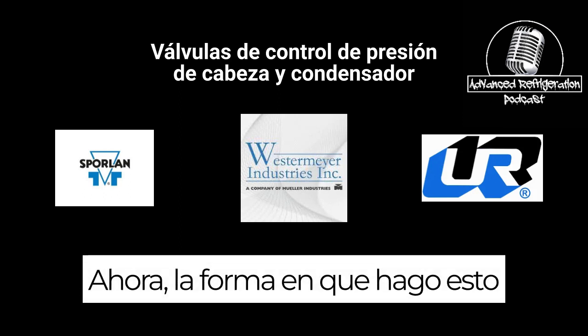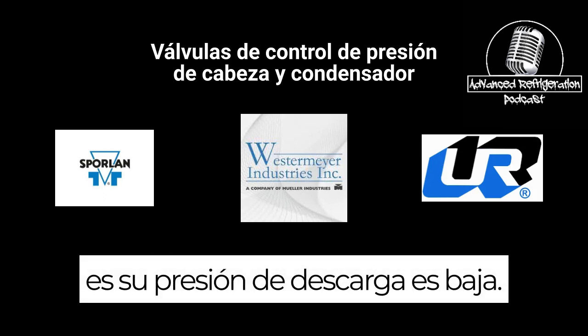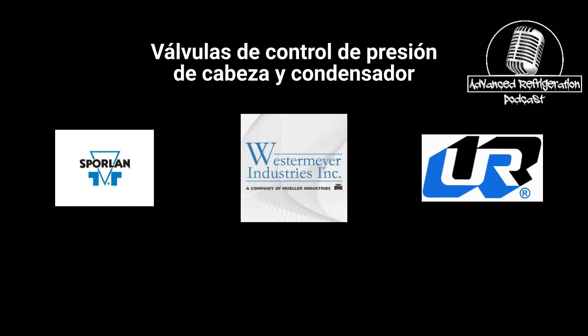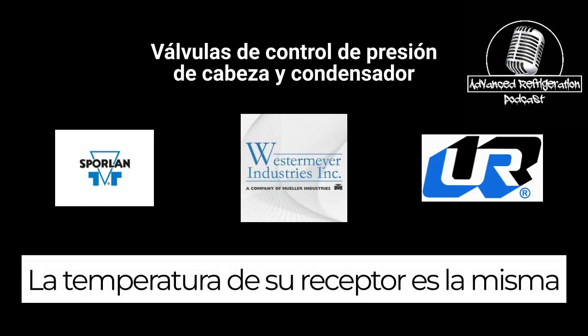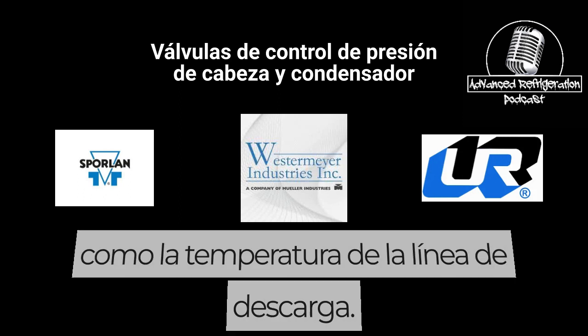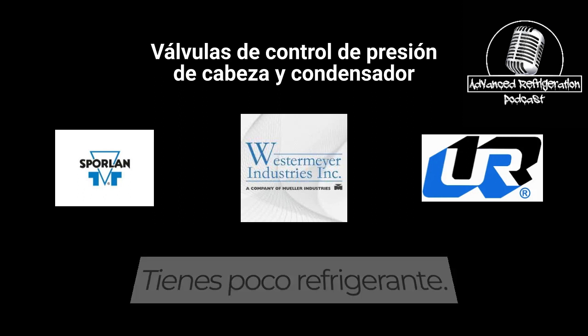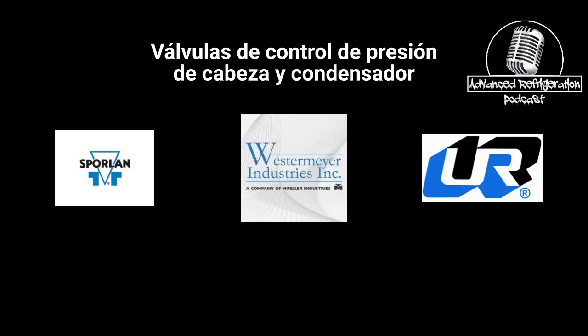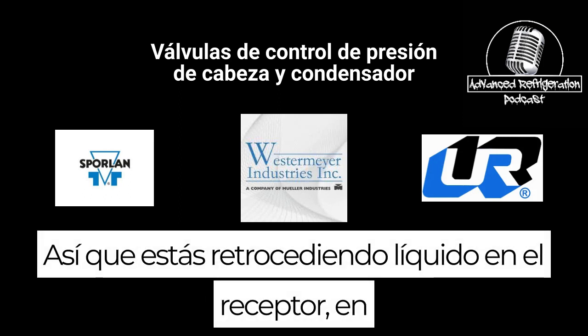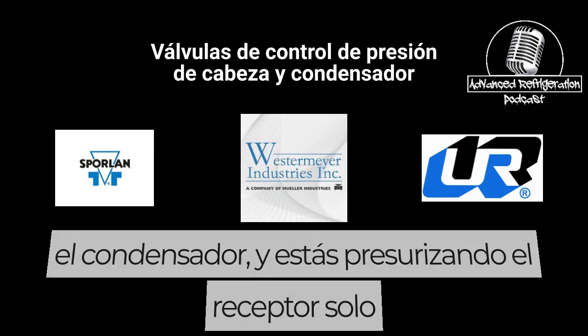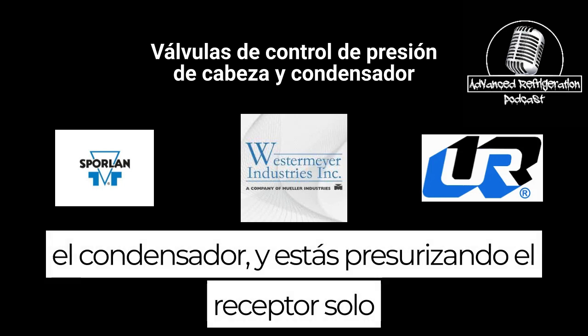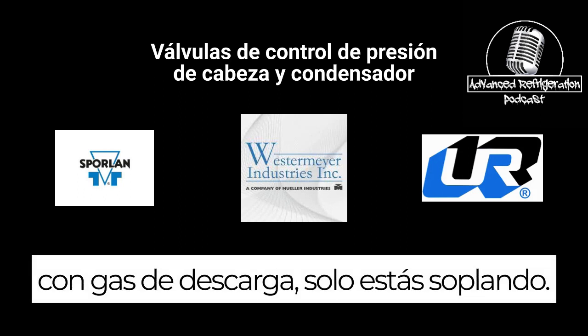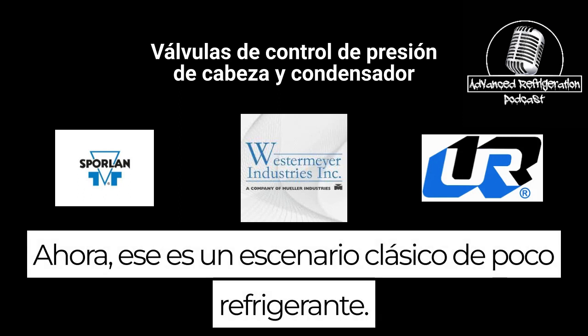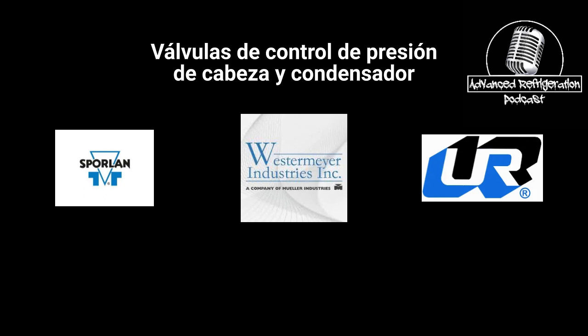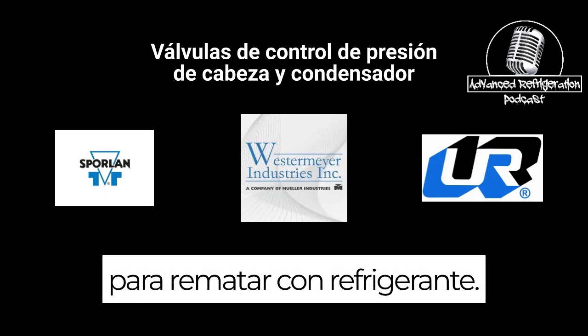Now, the way I do this is, if your discharge pressure is low and your receiver temperature is the same as the discharge line temperature, you are low on refrigerant. So you're backing liquid up in the receiver and the condenser, and you're pressurizing the receiver with just discharge gas. You're just blowing through. That is a classic low on refrigerant scenario, so you need to top off the refrigerant.